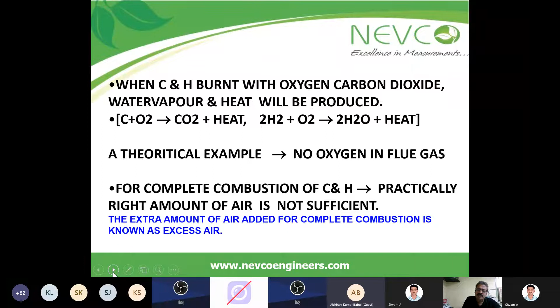The principle of burning, whether solid, liquid or gas, whatever fuel you're using, requires air. The main content of all fuels is carbon and hydrogen. When carbon and hydrogen bond with oxygen, carbon dioxide, water vapor and heat are produced. This is a simple equation: C plus O2 gives CO2 plus heat. In a theoretical example, there is no oxygen in the flue gas, but for complete combustion of carbon and hydrogen, practically the right amount of air is not sufficient. The extra amount of air added to complete the combustion is known as excess air. Excess air has to be added, and only then will the fuel be properly burned.